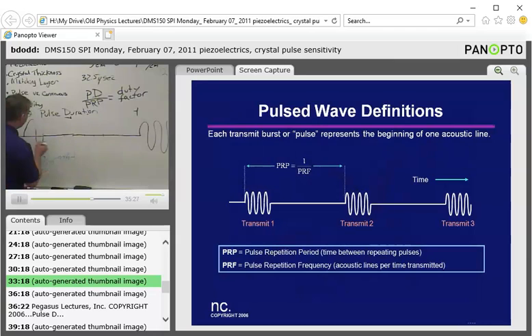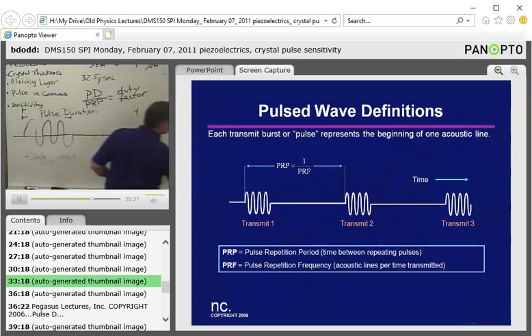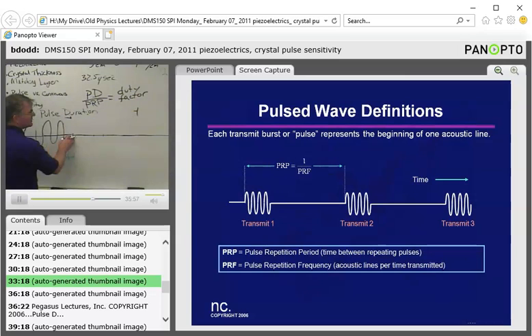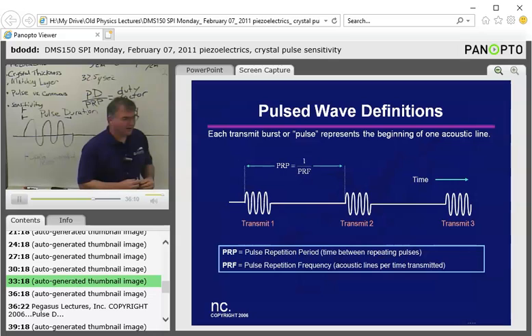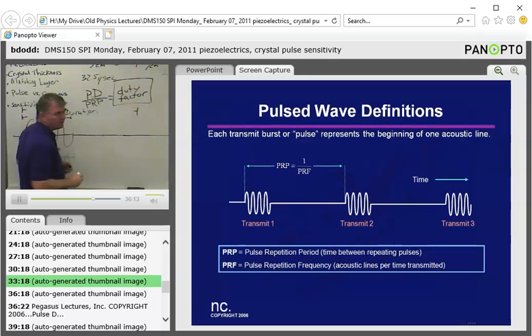Now if we keep our normal duty factor and we increase our pulse repetition period, so instead of stopping here, I'm going to come way down here. This is actually not drawn to scale, by the way. Now my pulse duration is still the same length, still a short pulse duration, but my pulse repetition period is a long time. So what has happened to the duty factor? It's gone way down, hasn't it? So for biological effects, we want to keep this duty factor as low as possible.